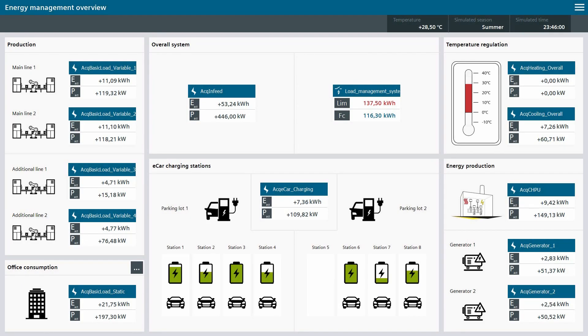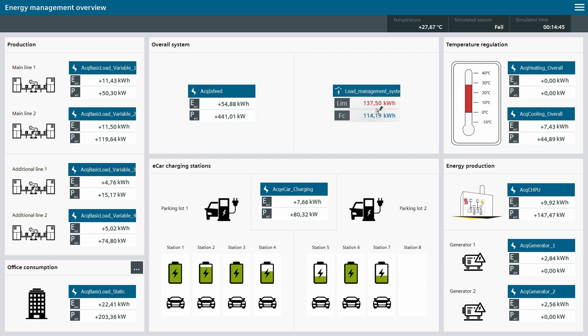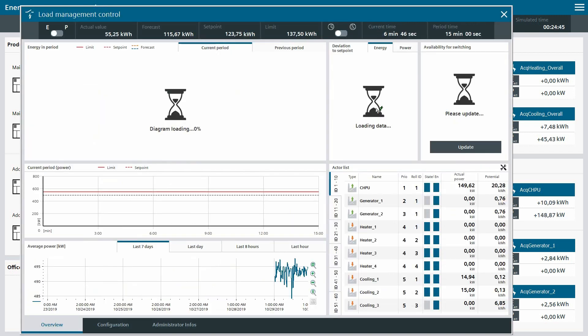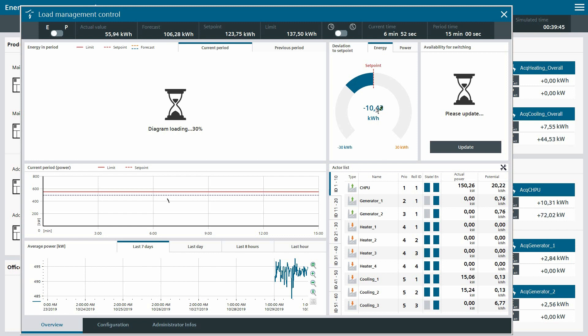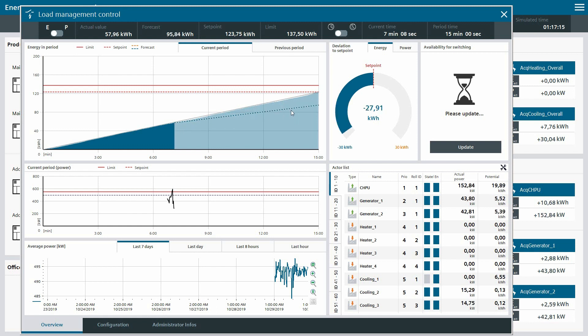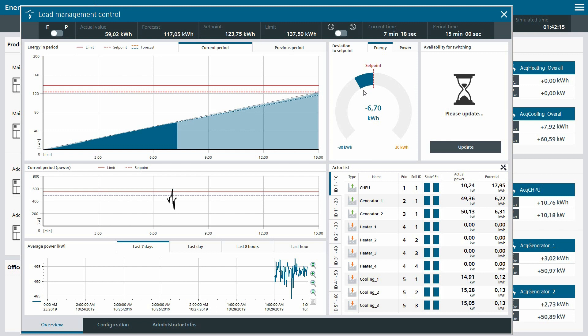As a last step, we show you the visualization of the load management system during runtime and the final phase of the configuration. The faceplate of the load management overview signals the user if the forecast of the current period is above the setpoint for switching. After activating the screen, the relevant data will be loaded and the current status of the complete load management system will be provided for the user. On the upper left side, the user gets the information about the energy consumption of the current and previous period, as well as the forecast. Here, visualized with a dashed line at the end of the period.